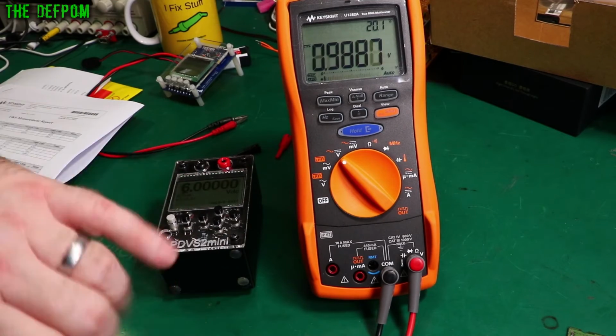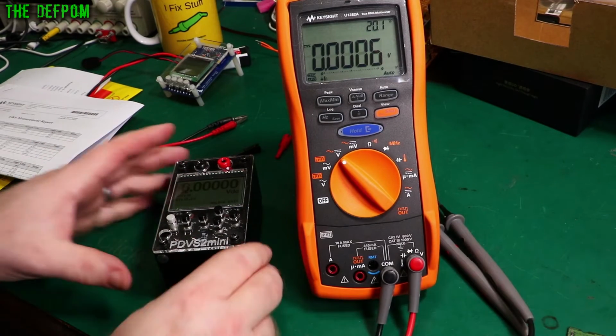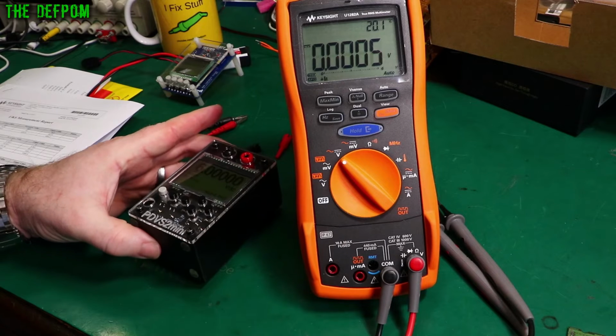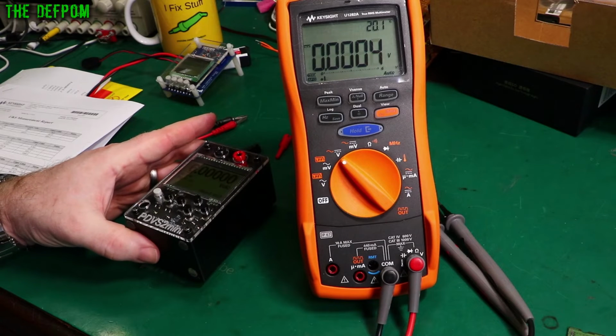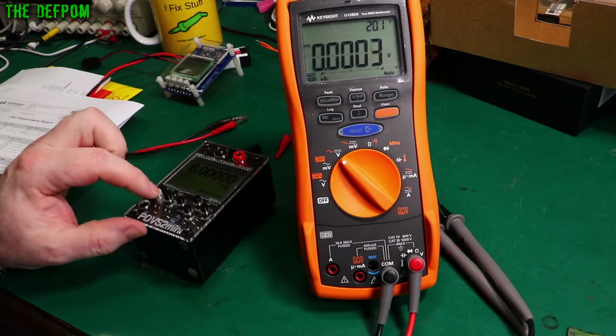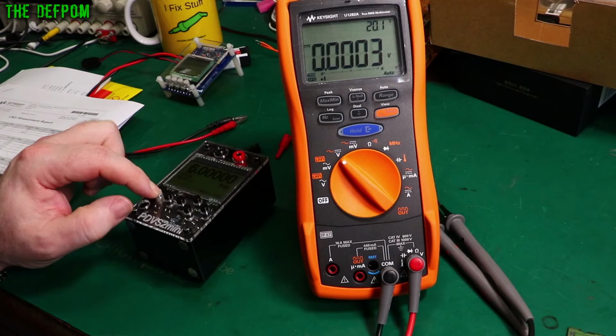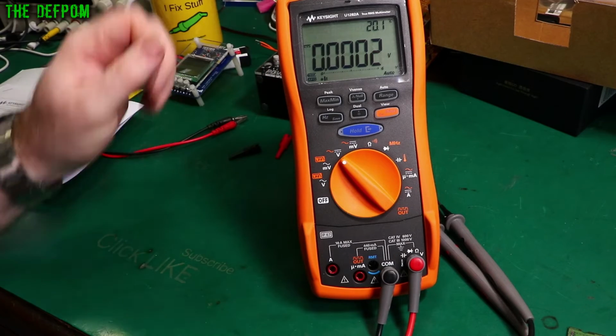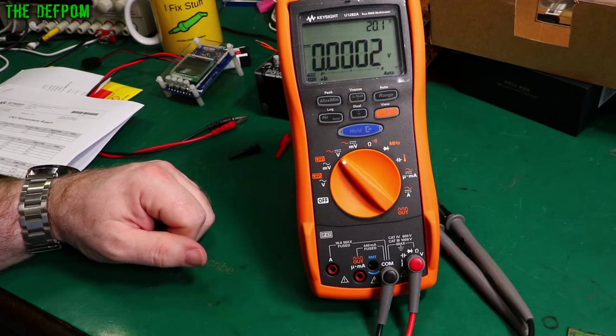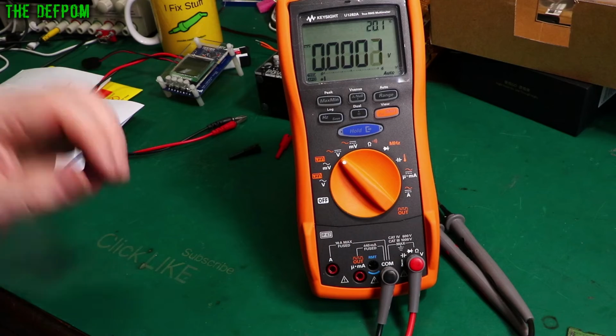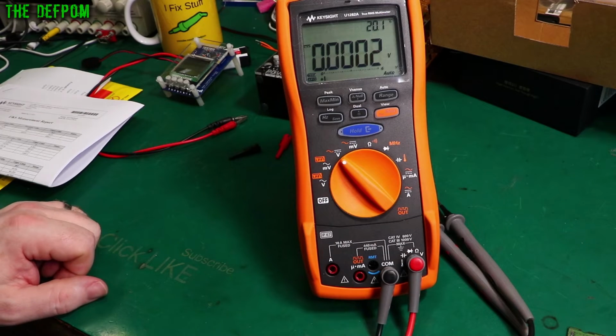So I can check this in a lot more detail once I go to the calibrator, because we can check every voltage calibration point from AC and DC and just verify that what I'm getting here matches what Keysight said they got. Of course, Keysight's equipment's going to be better than what I've got here by far, and it'll also be currently calibrated, whereas my stuff isn't. It's just good to do a cross check and see if anything looks completely out of whack, because it can happen.